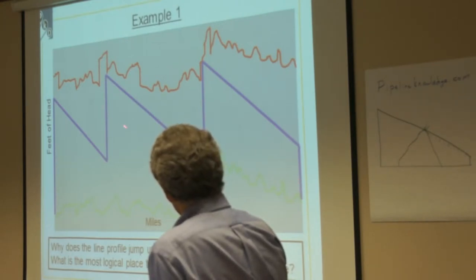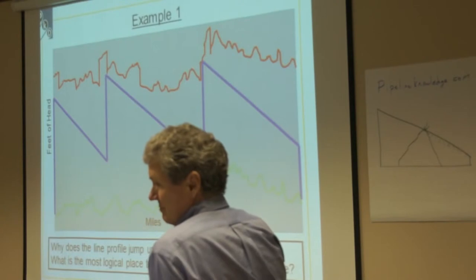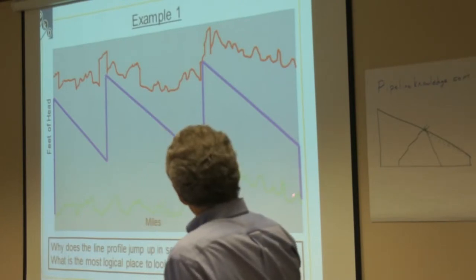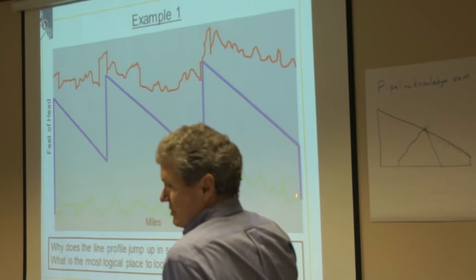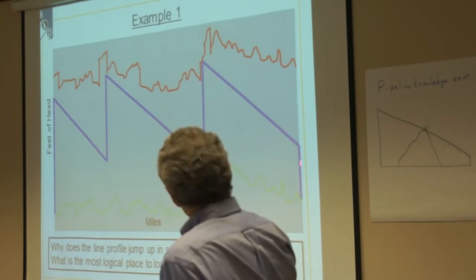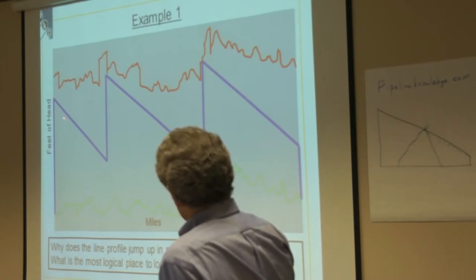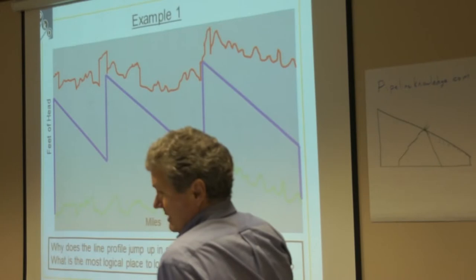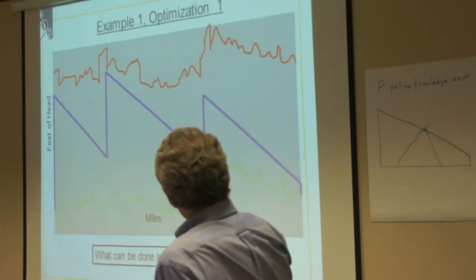Or you might be able to drop this down there and do like that. So that's the first place you'd look and you'd say, maybe there's a good reason for this and maybe there isn't. Can I reduce this amount of back pressure here so that I'm not throttling out that pressure? You could still run at the same flow rate because the slope of these gradients are really what determines your flow rate.